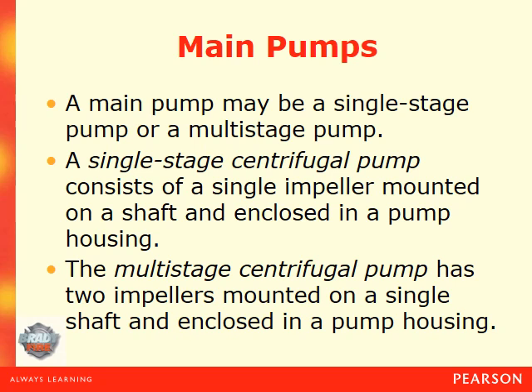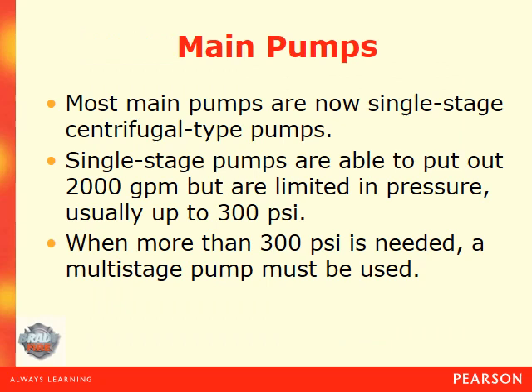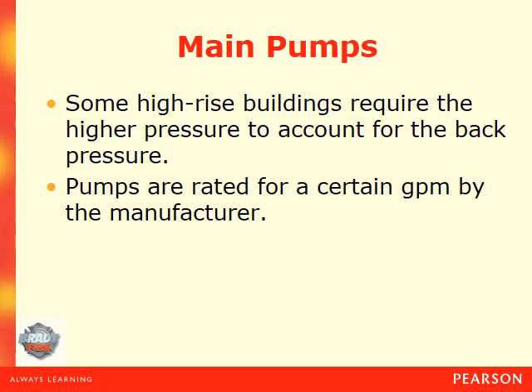A main pump may be a single stage or multi-stage pump. A single stage centrifugal pump consists of a single impeller mounted on a shaft and enclosed in a pump housing. The multi-stage centrifugal pump has two impellers mounted on a single shaft. Most main pumps are now single stage centrifugal type pumps. Single stage pumps are able to put out 2,000 gallons per minute but are limited in pressure, usually up to 300 psi. When more than 300 psi is needed, a multi-stage pump must be used. Some high-rise buildings require the higher pressure to account for back pressure.